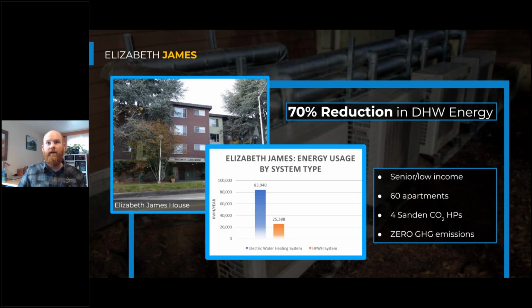And here's another project. This is a retrofit project that was done around 2015, 2016. Elizabeth James House. This was an existing building. It's serving senior low-income tenants. There are 61 bedroom apartments. And we reutilized the existing system and essentially put 4 Sanden CO2 heat pump water heaters as the preheat before the existing electric resistance water heating system.